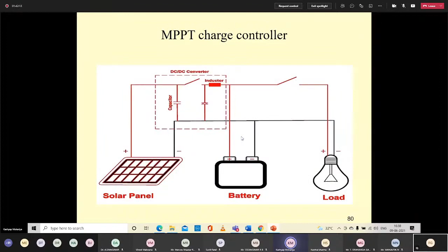MPPT charge controllers use a small DC-DC converter, which might be buck, boost, or buck-boost depending on the condition. The MPPT charge controller extracts maximum power from the PV module by forcing it to operate at a voltage close to the maximum power point. It adjusts its input voltage to utilize the maximum power output of the solar array and transforms this power to supply the varying voltage requirement, with input voltage varied by the DC-DC converter. MPPT controllers have an adaptive algorithm that follows the maximum power point of the solar array and adjusts the incoming voltage to maintain the most efficient amount of power for the system.